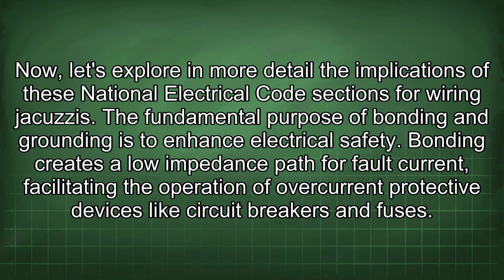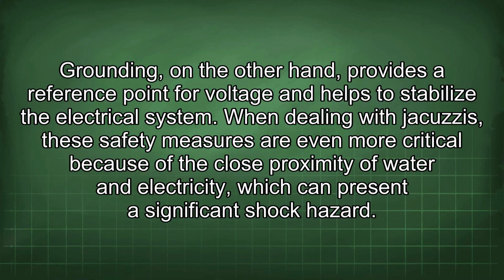The fundamental purpose of bonding and grounding is to enhance electrical safety. Bonding creates a low impedance path for fault current, facilitating the operation of overcurrent protective devices like circuit breakers and fuses. Grounding, on the other hand, provides a reference point for voltage and helps to stabilize the electrical system. When dealing with jacuzzis, these safety measures are even more critical because of the close proximity of water and electricity, which can present a significant shock hazard.